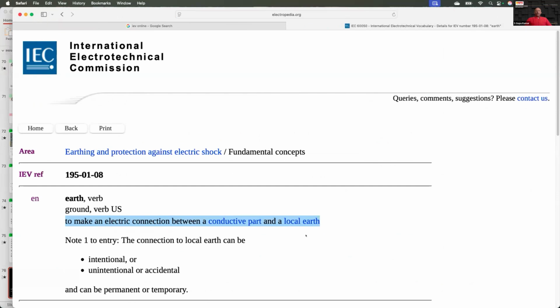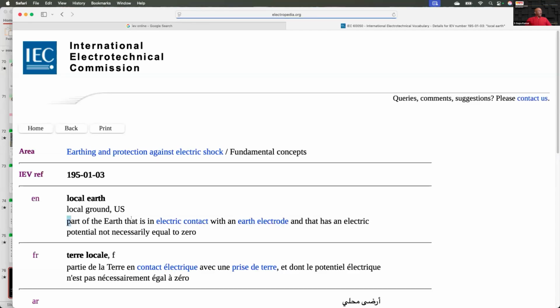It means you take a wire and connect two items. One is a conductive part, one is a local earth. That is earthing. Now, what is this local earth? Part of earth that is in electric contact with an earth electrode and has an electric potential, not necessarily zero. And the process of making this connection is called earthing.